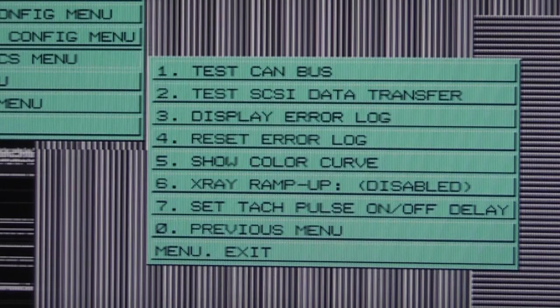Particularly if it's not been turned on for a long time, if you ramp it up very slowly, apparently it helps improve the lifetime. Now, I've seen a couple of things describing this process as seasoning the tube. There's a couple of different explanations I've seen. One is that the sudden heating of the target after it's been not used for a while can cause cracking.